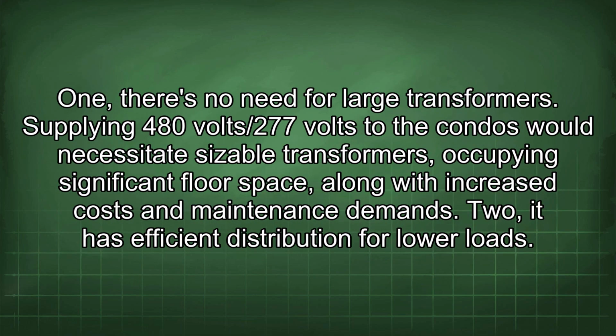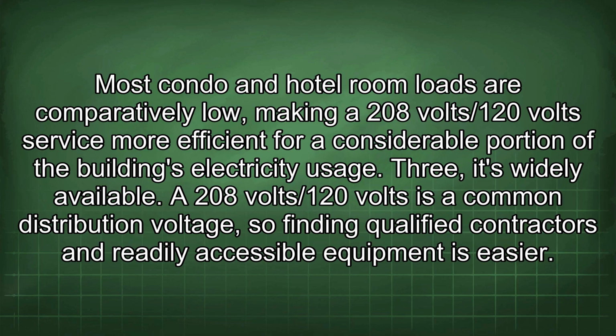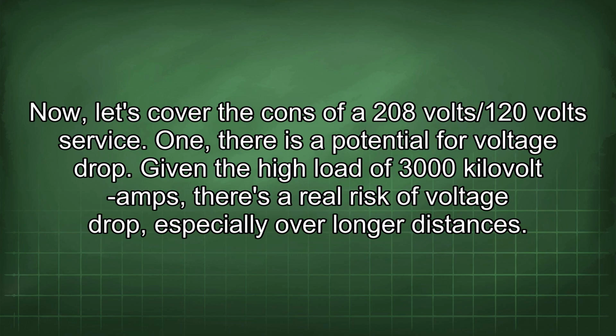1. There's no need for large transformers. Supplying 480 volts/277 volts to the condos would necessitate sizable transformers occupying significant floor space, along with increased costs and maintenance demands. 2. It has efficient distribution for lower loads. Most condo and hotel room loads are comparatively low, making a 208 volts/120 volts service more efficient for a considerable portion of the building's electricity usage. 3. It's widely available. A 208 volts/120 volts is a common distribution voltage, so finding qualified contractors and readily accessible equipment is easier. Now let's cover the cons of a 208 volts/120 volt service.